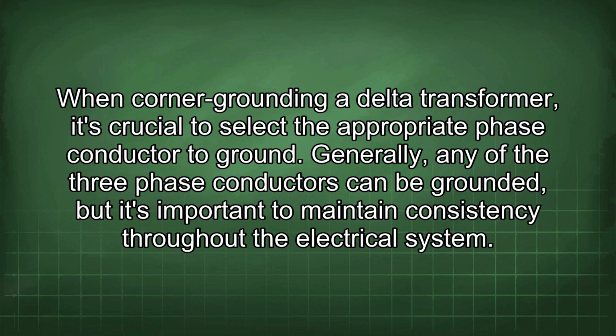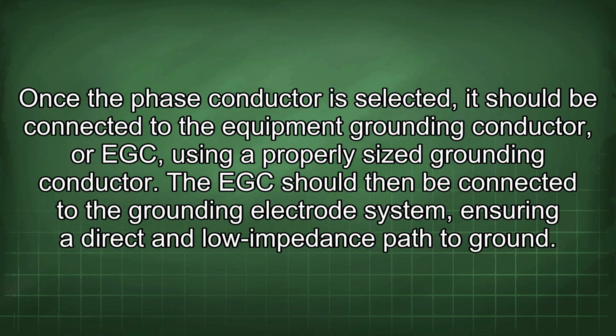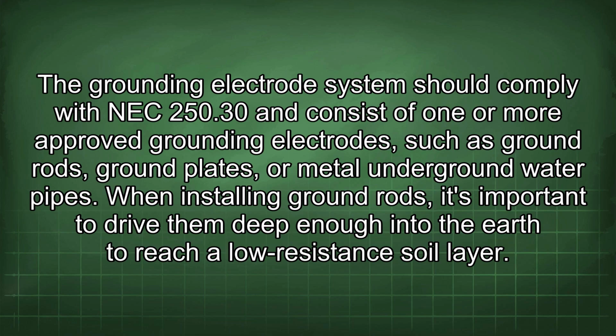When corner grounding a delta transformer, it's crucial to select the appropriate phase conductor to ground. Generally, any of the three phase conductors can be grounded, but it's important to maintain consistency throughout the electrical system. Once the phase conductor is selected, it should be connected to the equipment grounding conductor, or EGC, using a properly sized grounding conductor. The EGC should then be connected to the grounding electrode system, ensuring a direct and low impedance path to ground. The grounding electrode system should comply with NEC 250.30 and consist of one or more approved grounding electrodes such as ground rods, ground plates, or metal underground water pipes.